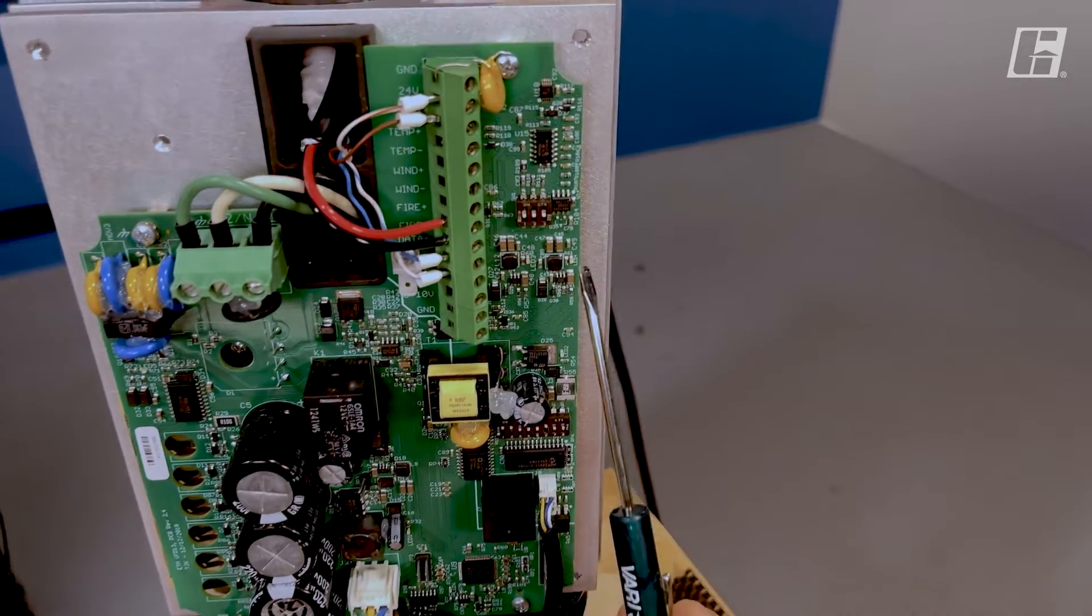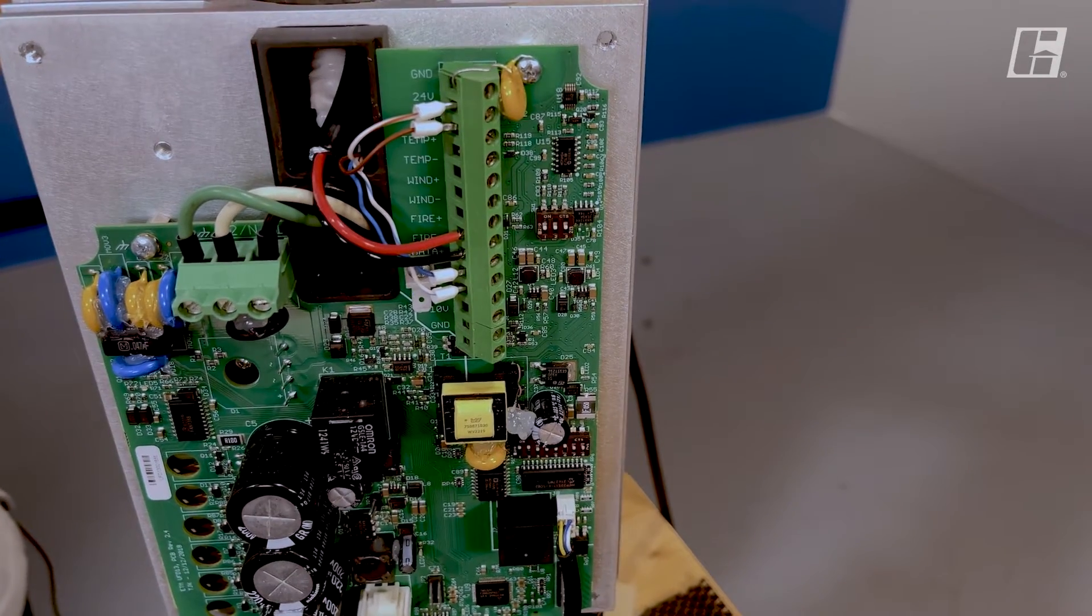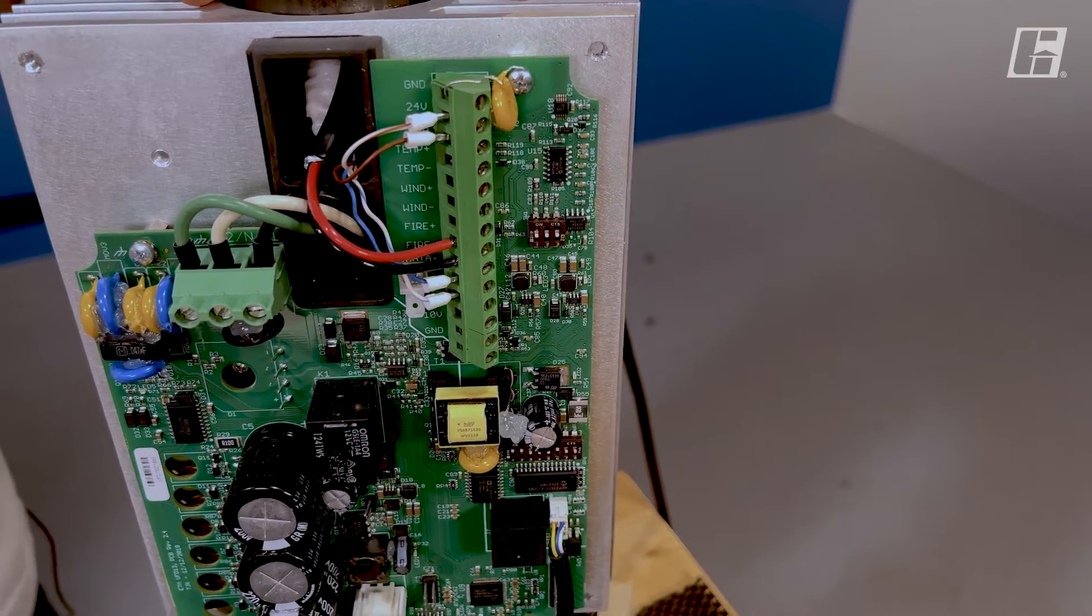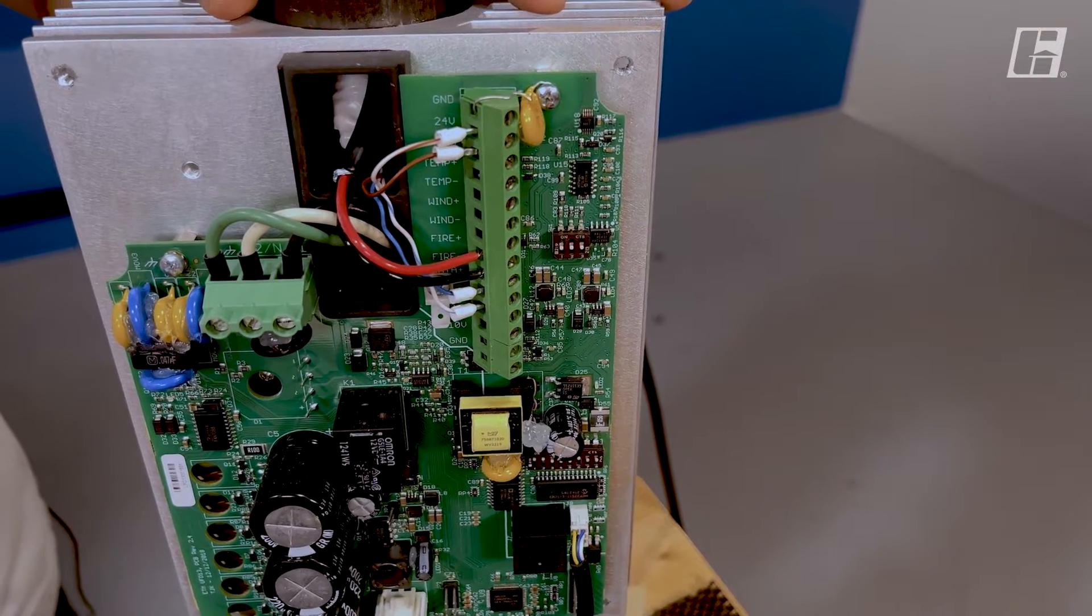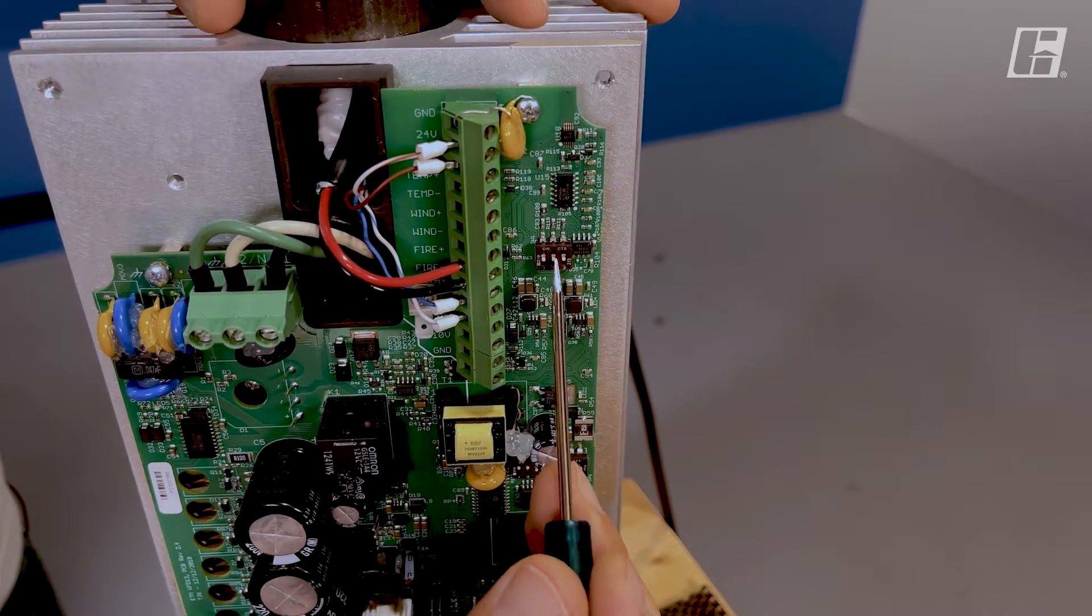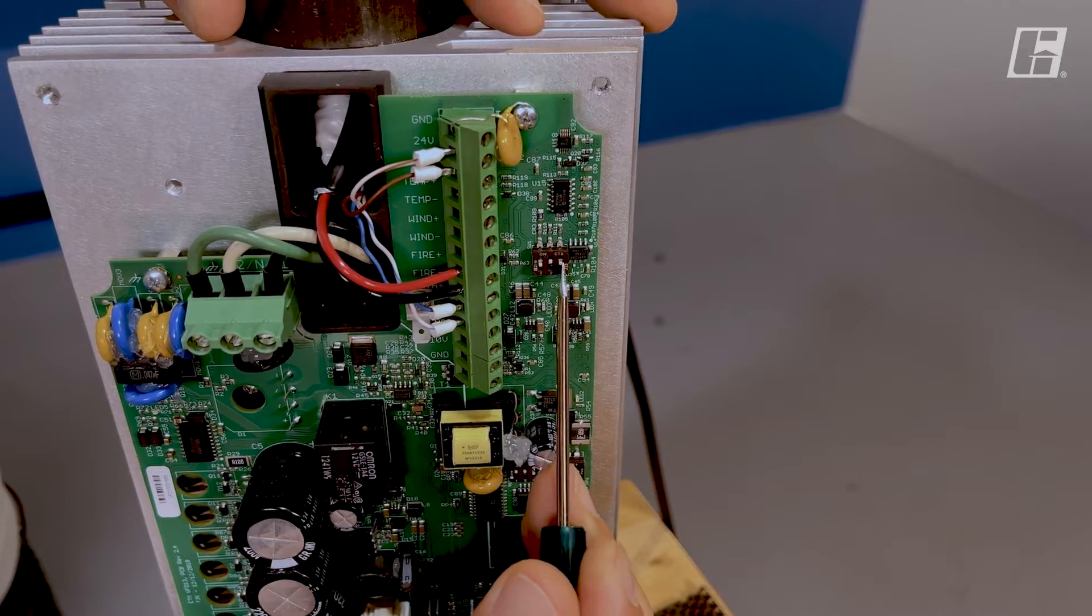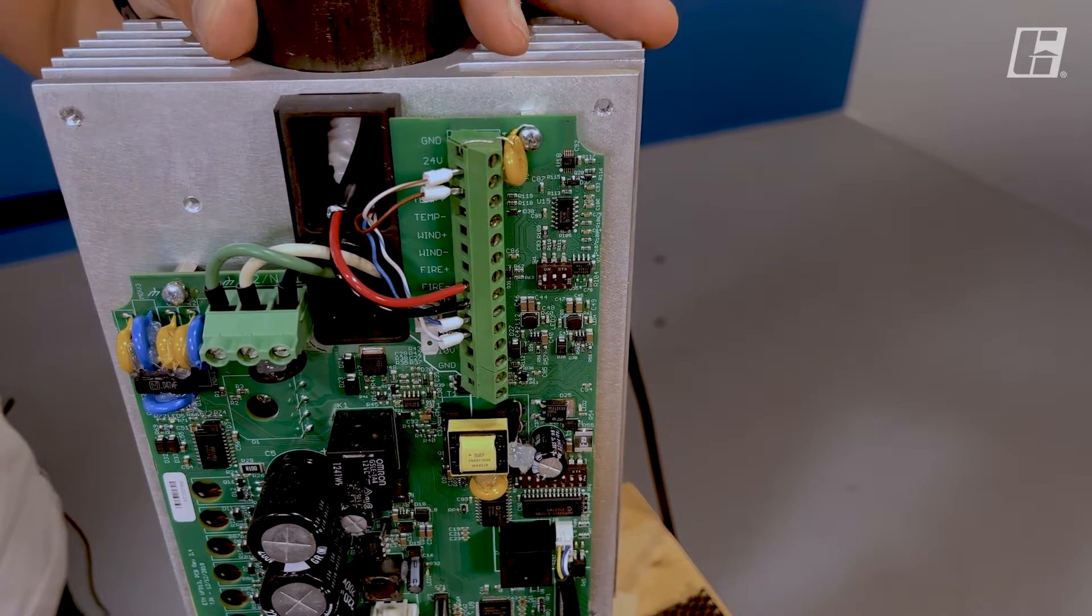We have a dip switch which sets up the communication biasing. This will either be set to down, up, up for the first fan in the series, or down, down, down for all additional fans. To set this for the first fan in the series, again, down, up, up.